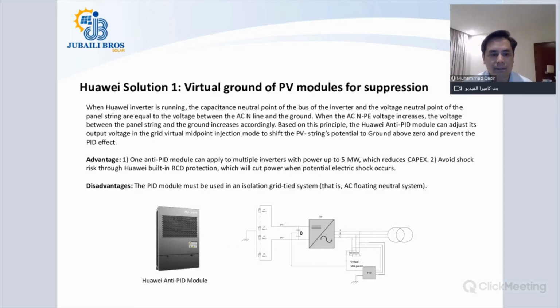What is the disadvantage? Being frank, the PID module must be used in an isolation grid tie system. So what does it mean? So you cannot use the Huawei Anti-PID module in case you are not using an IT grid connected network. So you must be using an IT grid connected network where you are not using the neutral side of the inverter.